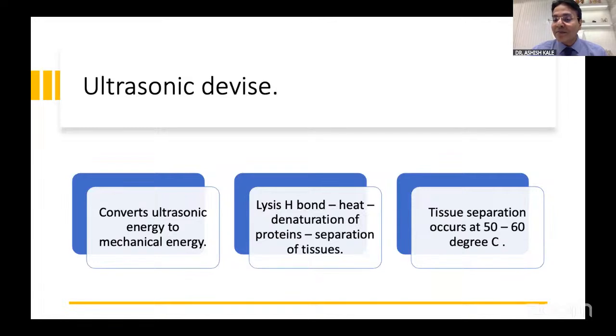Then there is always the problem of what harmonic setting one should be using and what setting usually causes coagulation. My friends, when you are using this instrument, it has a jaw and it has a tip. When you use the jaw for coagulation for a longer time, it causes more coagulation. When you use the tip as a dissector, it usually causes coagulation of the smaller capillaries, and when you use the jaw to grasp the tissue, it will cause more coagulation.